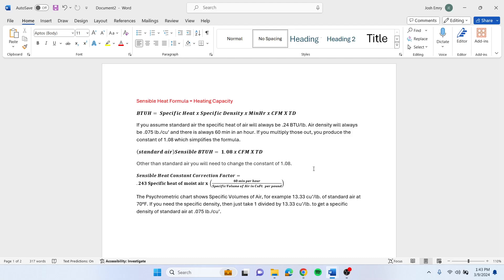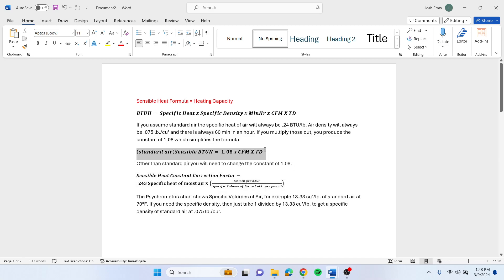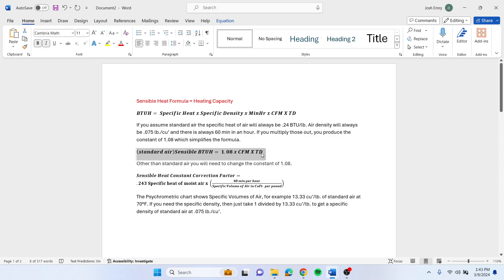If you're trying to figure out how much heat you've added to the air by going across the coil or a heat exchanger, then you can use the standard air formula. You've probably seen this before where the BTUs per hour equals 1.08 times CFM times your temperature difference or Delta T.